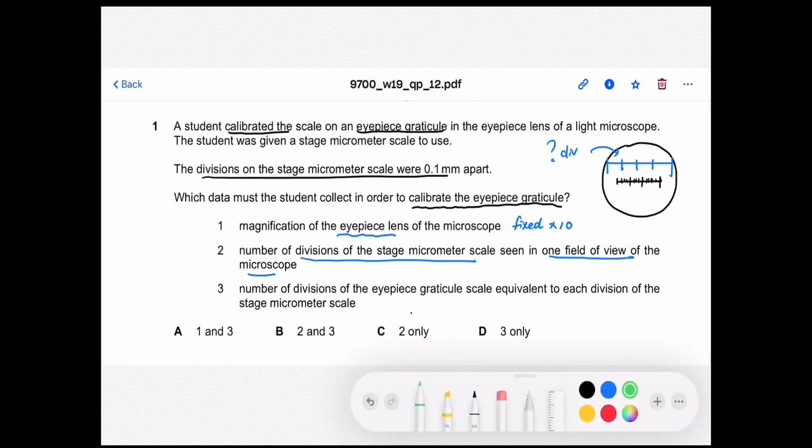I just need to calibrate by matching the number of divisions on the stage with the eyepiece. The total number of divisions doesn't really matter. So, number two is out.